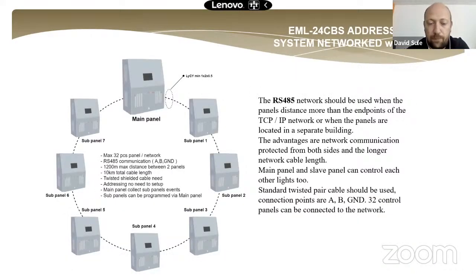I talk about the networking of the panel. Here we can see the RS485 network. 32 panels can be connected to each other in an RS485 network. The distance between two panels can be a maximum of 1.2 kilometer. So it's very good if you have different buildings on one site and you have to connect the panels to each other, but the TCP/IP networking cable length is too much, or you can't use the local area network. You can connect the panels to each other with RS485 network cable. It's a simple twisted 2-core cable with shielding, similar to what you use in fire alarm networking.